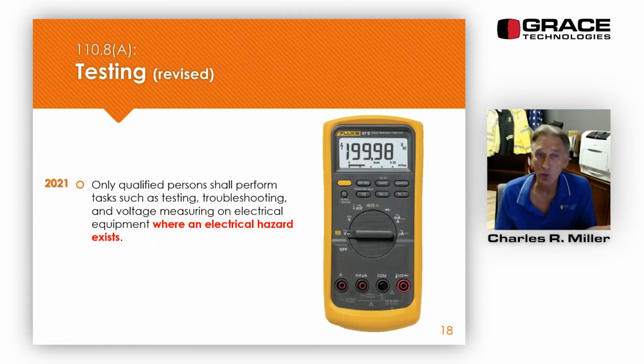In 110.8(A), this is in a different section. Remember, our steps are in 120, but this is 110. I wanted to bring this up. Only qualified persons shall perform tasks such as testing, troubleshooting, and voltage measuring on electrical equipment where an electrical hazard exists. So the person doing the voltage testing for absence of voltage has to be a qualified person.